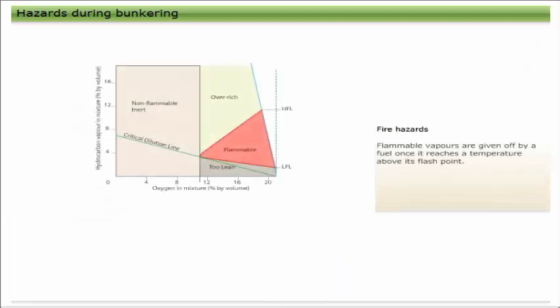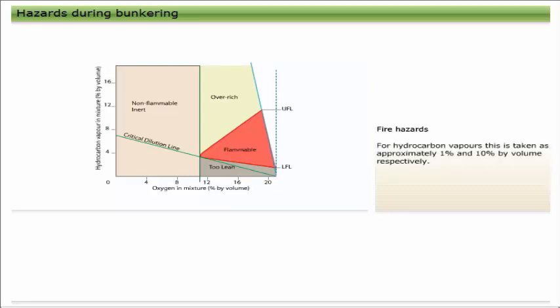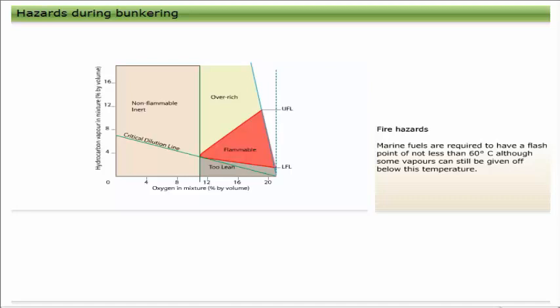Flammable vapors are given off by fuel once it reaches a temperature above its flashpoint. The flashpoint is defined as the temperature at which vapors given off can be ignited by an external ignition source. When fuel vapor is mixed with the required amount of oxygen to form a flammable mixture and an ignition source is present, fire or explosion can occur. A flammable mixture has a concentration of vapor between the lower explosive limit and the upper explosive limit — for hydrocarbon vapors approximately 1% and 10% by volume respectively. To prevent fire or explosion it is necessary to either avoid formation of a flammable mixture or remove any possible ignition source. Marine fuels are required to have a flashpoint of not less than 60 degrees Celsius.